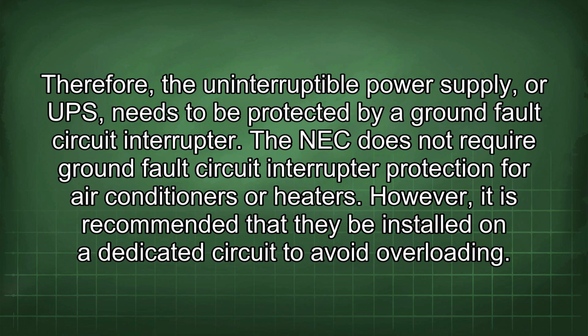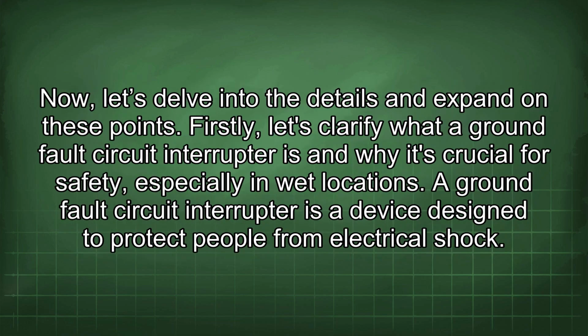interrupter. The NEC does not require ground fault circuit interrupter protection for air conditioners or heaters. However, it is recommended that they be installed on a dedicated circuit to avoid overloading. Now let's delve into the details and expand on these points. Firstly, let's clarify what a ground fault circuit interrupter is and why it's crucial for safety, especially in wet locations.